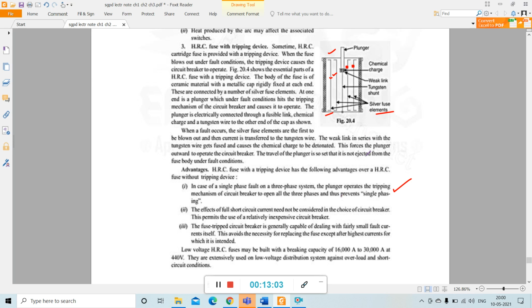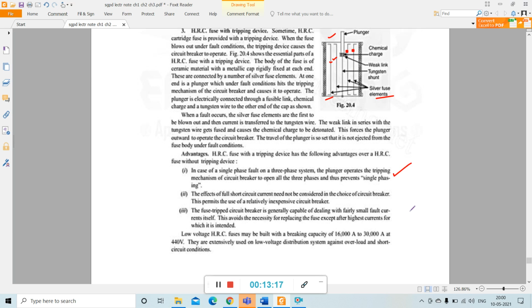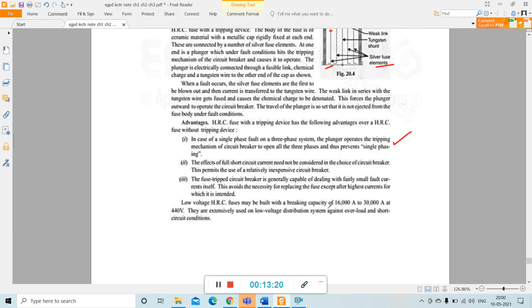The fuse tripped circuit breaker is generally capable of dealing with fairly small fault current itself. This avoids the necessity of replacing the fuse except after the highest current for which it is intended. Low voltage HRC fuses may be built with breaking capacity of 16,000 ampere to 30,000 ampere at 440 volt. They are extensively used on low voltage distribution systems against overload and short circuit conditions. Clearly understood about this? So these are all about low voltage fuses.